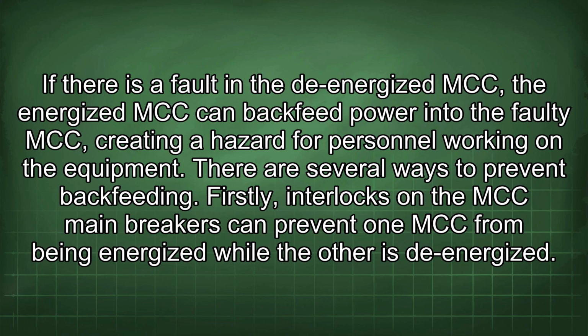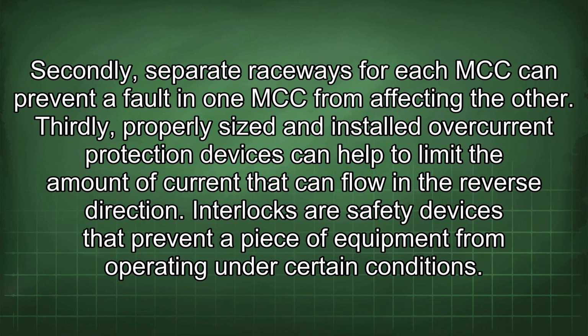There are several ways to prevent backfeeding. Firstly, interlocks in the MCC main breakers can prevent one MCC from being energized while the other is de-energized. Secondly, separate raceways for each MCC can prevent a fault in one MCC from affecting the other. Thirdly, properly sized and installed overcurrent protection devices can help to limit the amount of current that can flow in the reverse direction. Interlocks are safety devices that prevent a piece of equipment from operating under certain conditions.